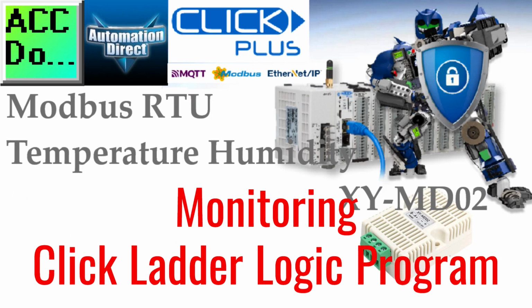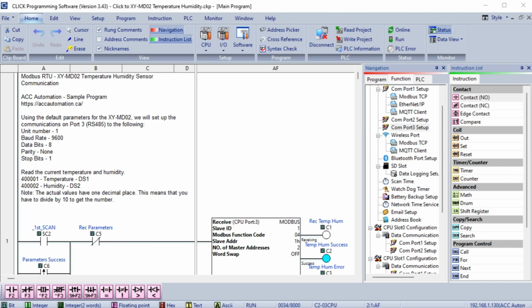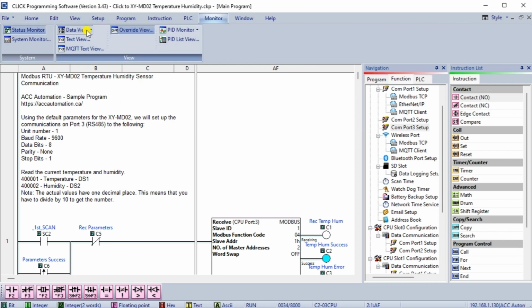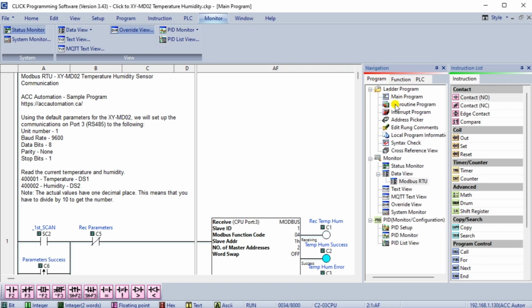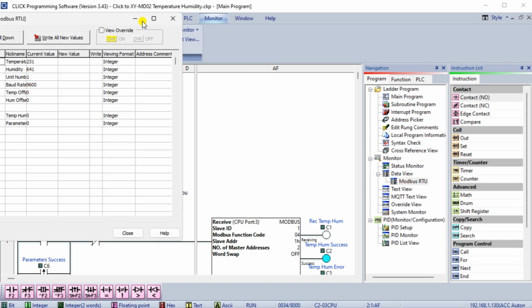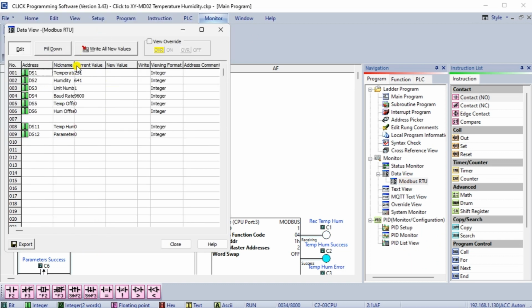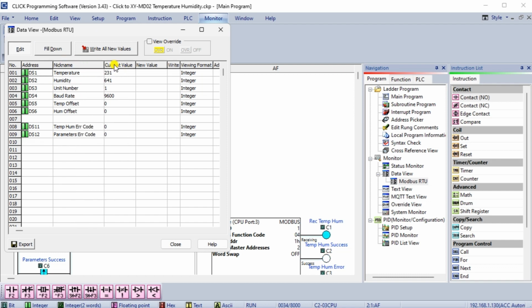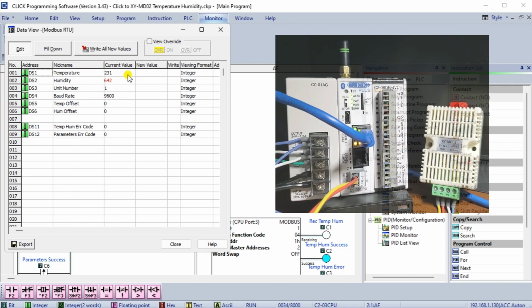Monitoring the Click ladder logic program. Using data view in the Click PLC programming software, we can watch the temperature, humidity, and parameters as the program runs. The temperature and humidity have 1 decimal place. This is understood, but if you need to display this on an HMI, divide the number by 10 and convert it to a real number in the PLC. DS1 is the temperature, which is 1 decimal in Celsius degrees. DS2 is the humidity in relative humidity as a percentage.